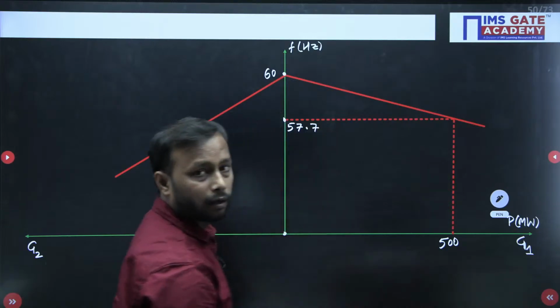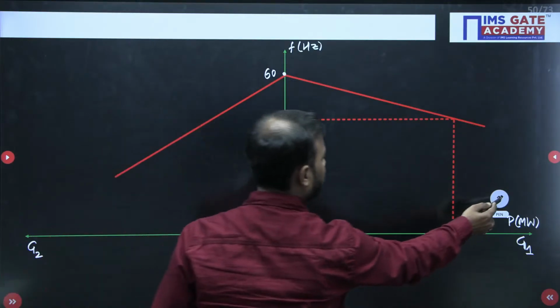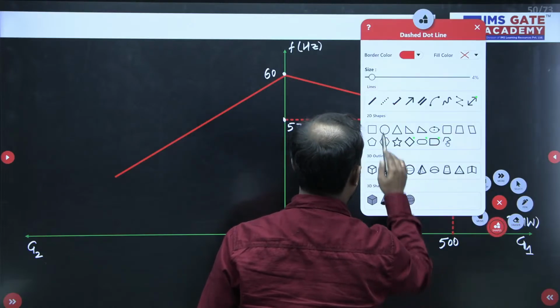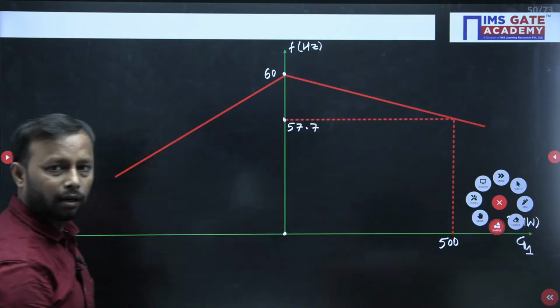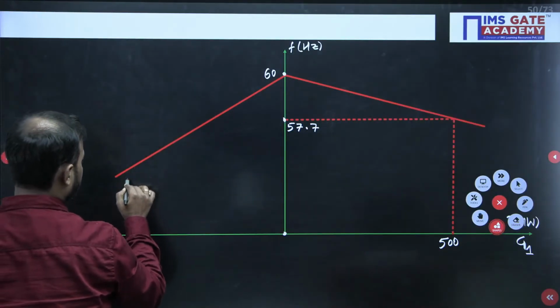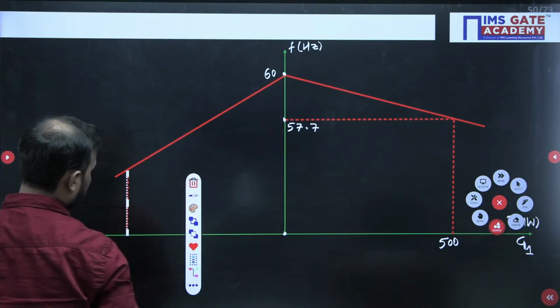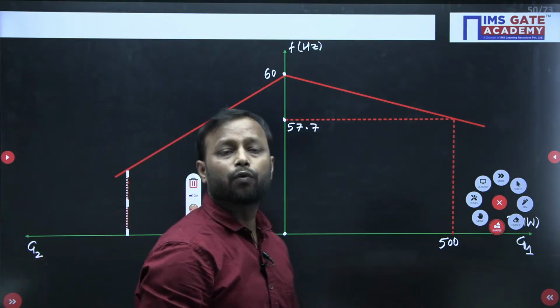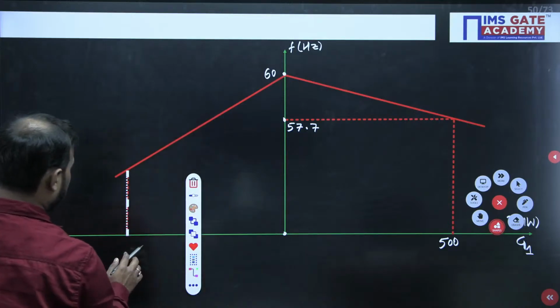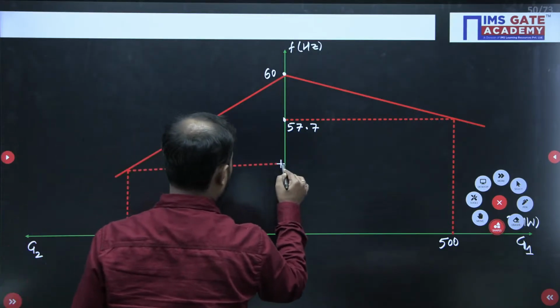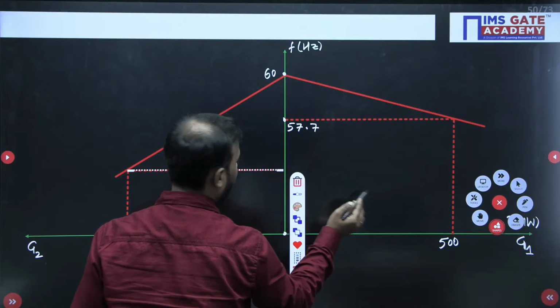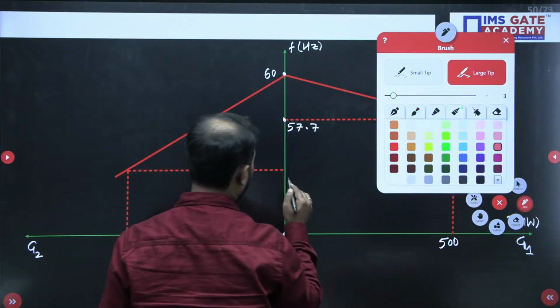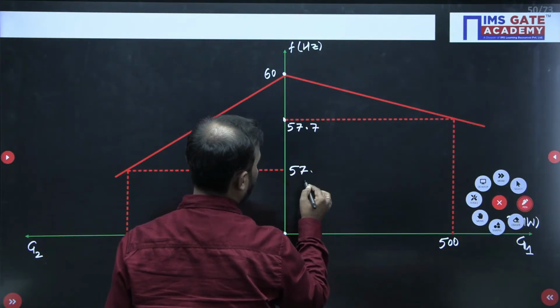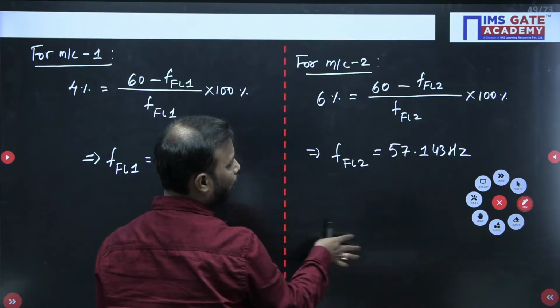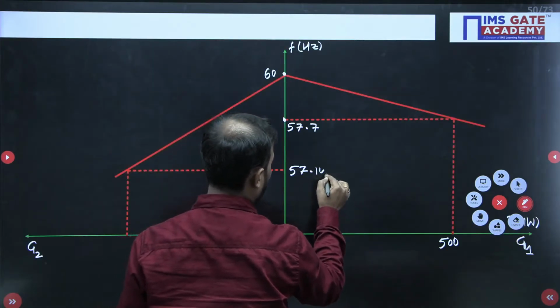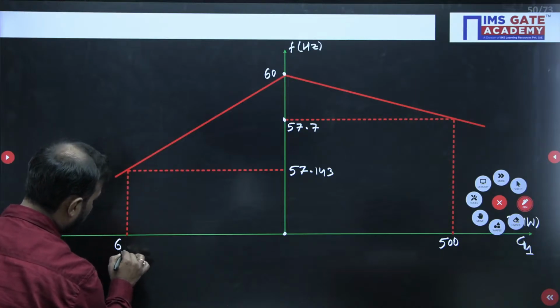In the same manner for generator 2, if the load would have been full load, then the full load frequency for generator 2 would have been 57.143, with full load being 600 megawatt.